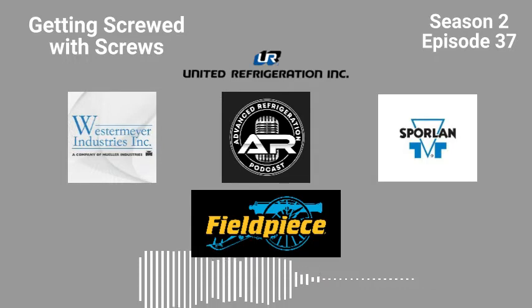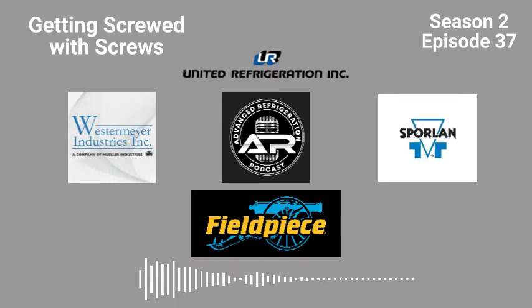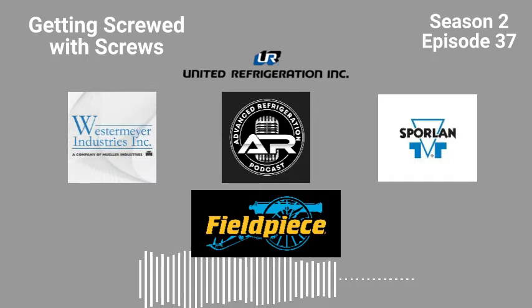Are you saying each compressor has its own filter? Nope. It's two filters off the main oil line. That's it. Oh shit. Yep. Okay, so they're in parallel with ball valves before and after, so you can just run one for the whole system. Correct. If you need to, you could bypass it. Because most of the racks I've seen are Hill racks. These are all Hill racks. Typically when they have the Bitzers, every single one has its own individual filter. Even the Hussmann screw racks I've seen. That's a Bitzer thing. Bitzers use those individuals, and a lot of times they have oil flow sensors built into the housing.